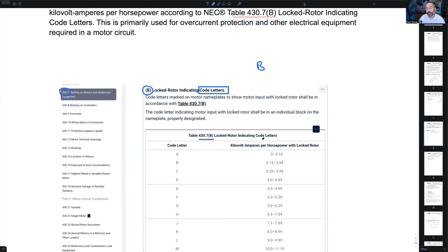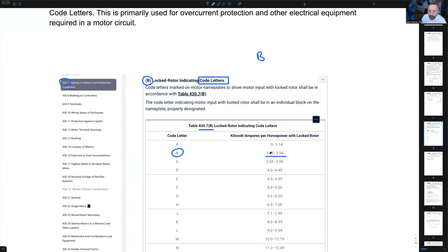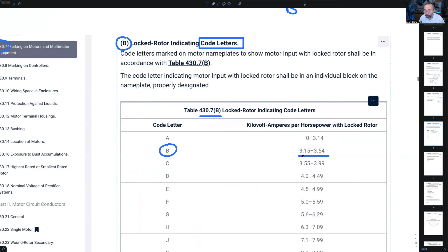And regardless of the voltage of the motor, if it's a B code letter, I know that at locked rotor conditions, when the motor is not energized and I push the button, the second it's energized, it's going to draw anywhere from 3.15 to 3.54 kVA per horsepower rating of that motor. And then from there, we could convert it to amps if we wanted to estimate the range of locked rotor current. Does that make sense?